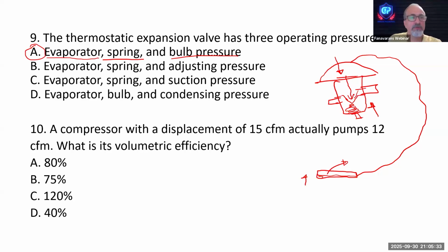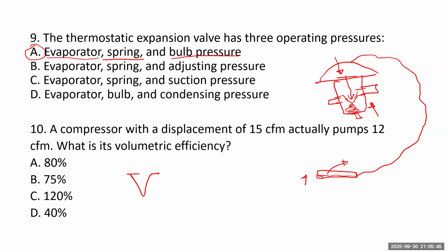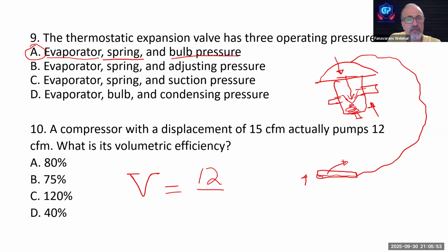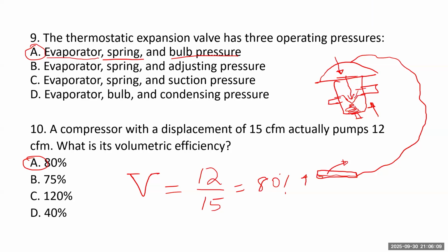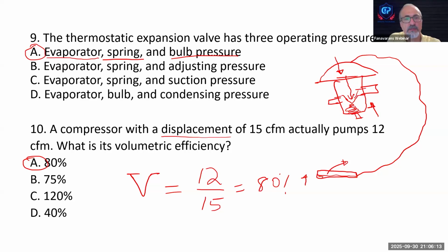Compressor, question number 10. A compressor with a displacement of 15 CFM, cubic feet per minute, actually pumps 12 CFM. What's the volumetric efficiency? It should be 80%. 12 by 15 is 0.8, times 100. The actual over the displacement, 12 over 15, is 80%. That's the volumetric efficiency. The displacement means the theoretical volume the compressor can move, and the actual is less than the theoretical.